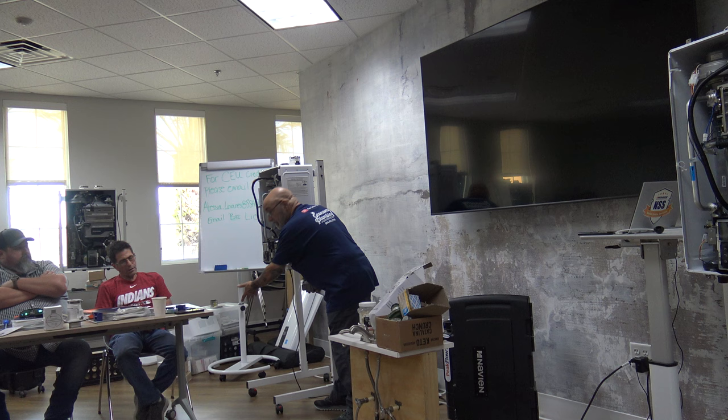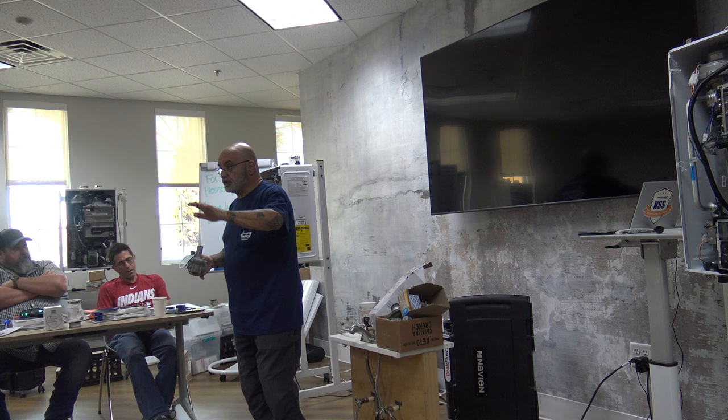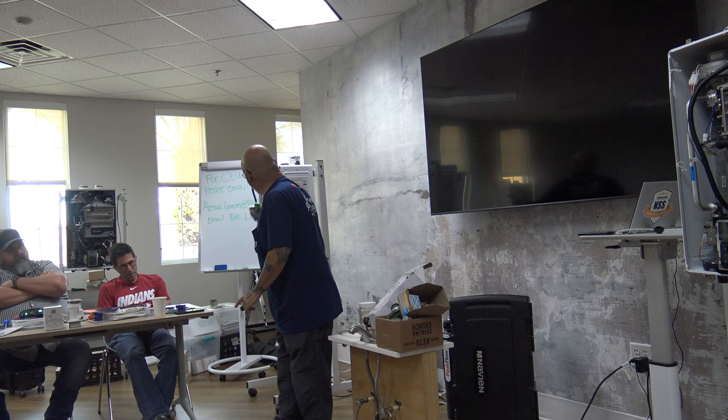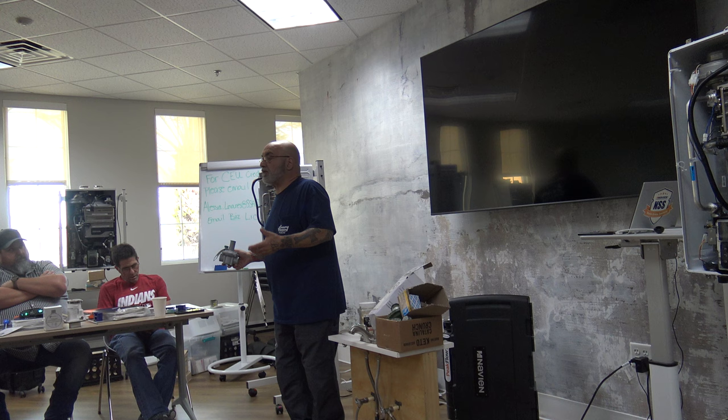I mean, excuse me, to have this thing correct. It's called regulator lockup. Regulators, yes, reduce the pressure, but when they're too close to the unit, especially a 199,000 BTU unit, they'll malfunction. Now, I know if there were some propane guys in here, they'd say, oh, well, I install them and they're only 6-10 inches away and it works. Well, it's got 12 pounds of pressure.